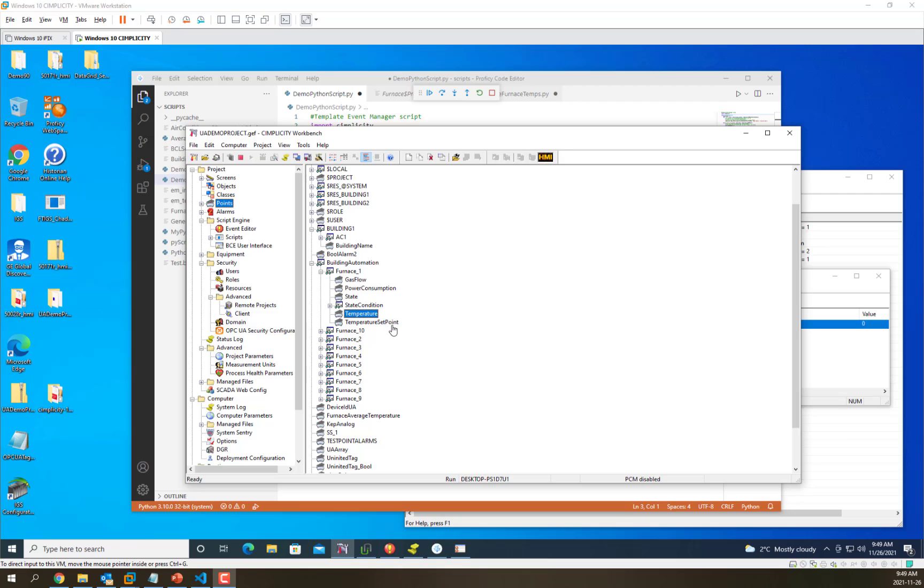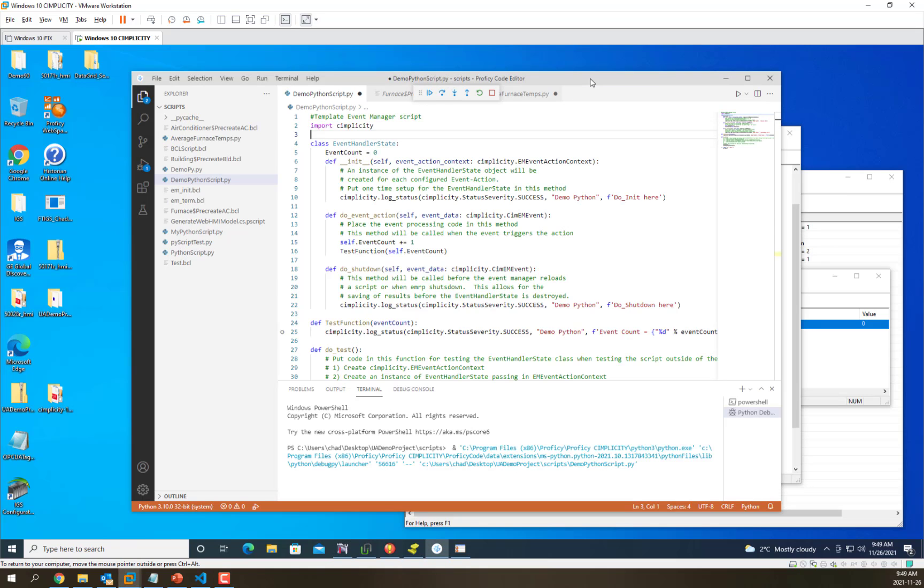Today we're going to use a Python script to average the furnace temperatures across all the furnaces in this building. As you'll recall from previous videos, we have a Python script that is triggered whenever a point changes, and we're going to reuse that script today and enhance it.